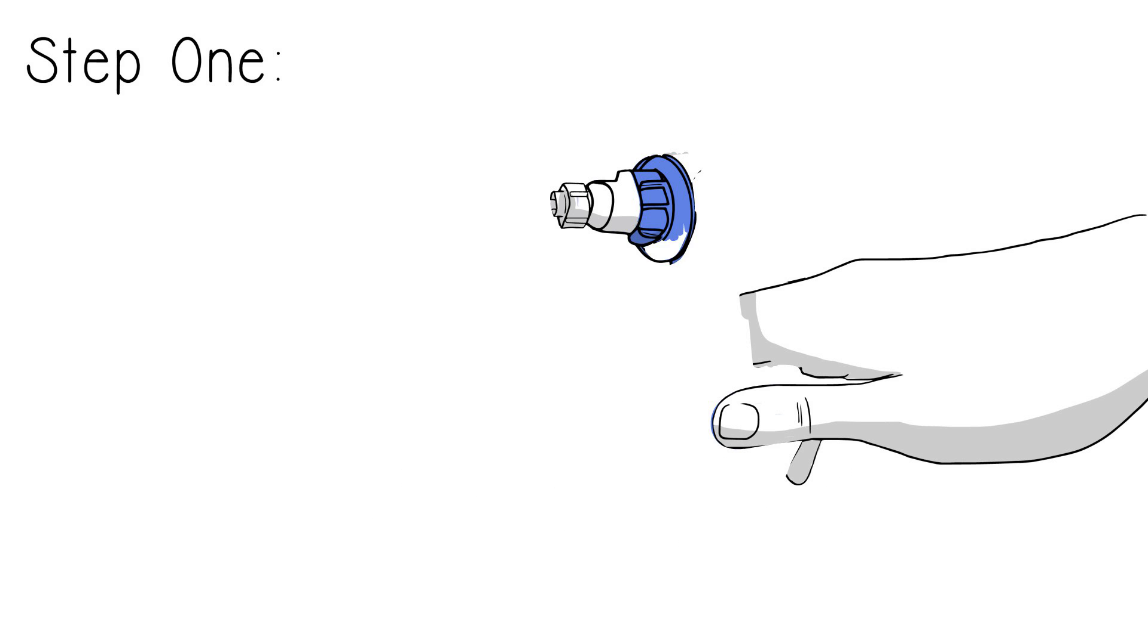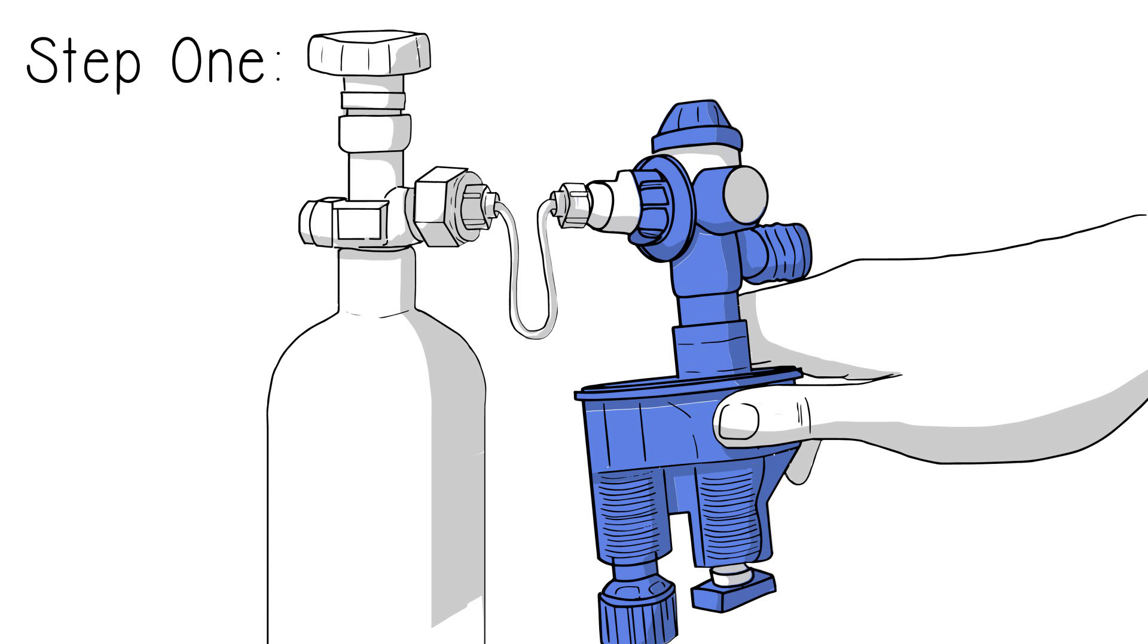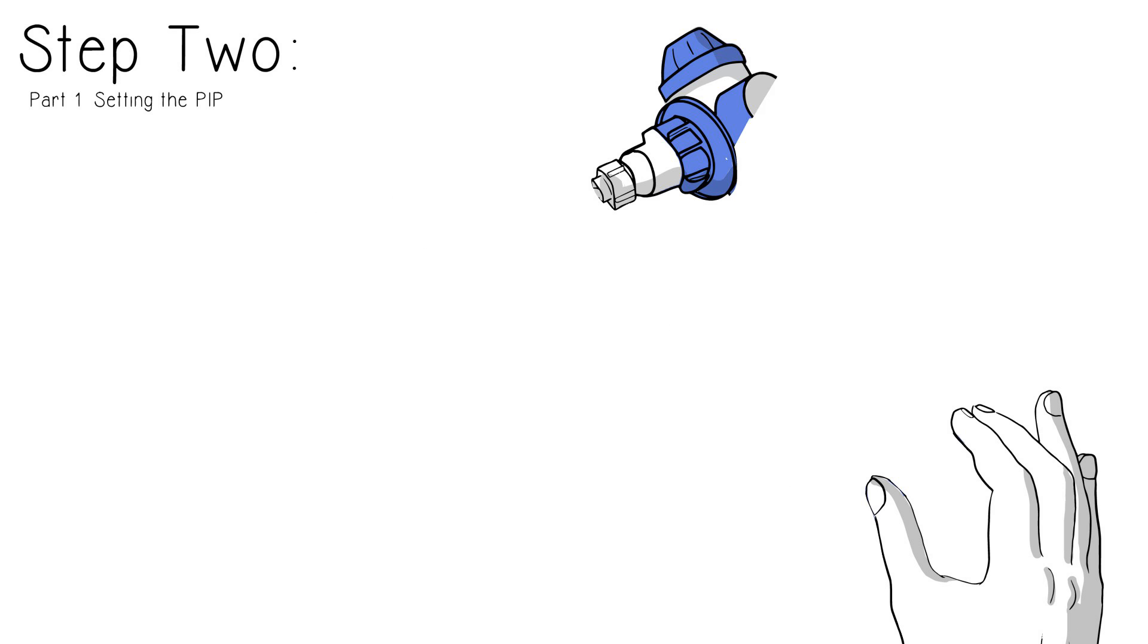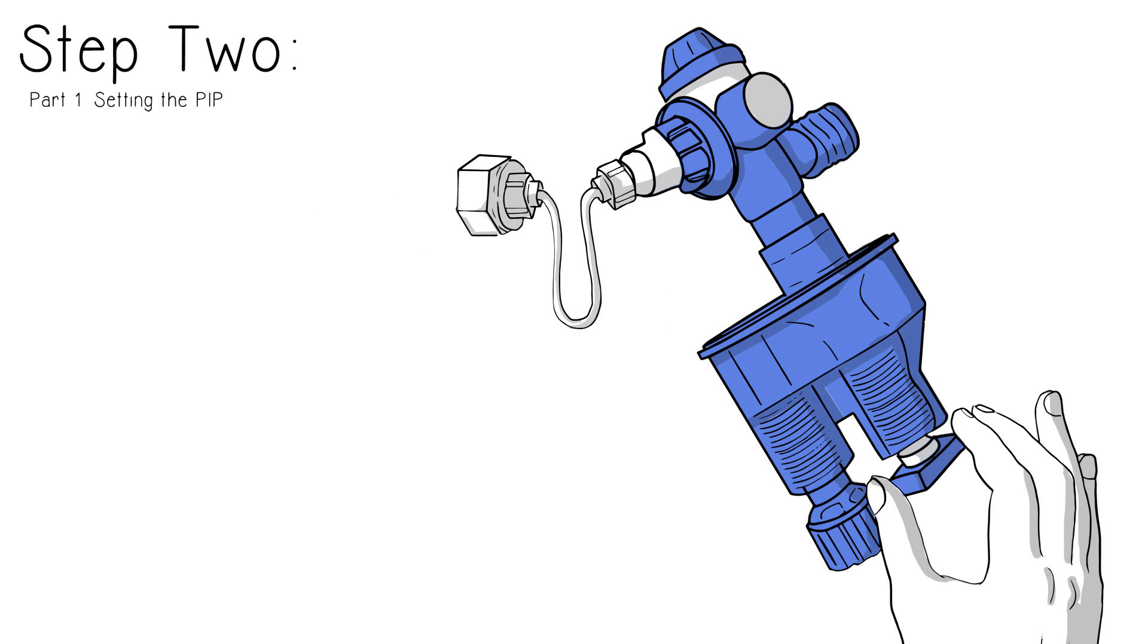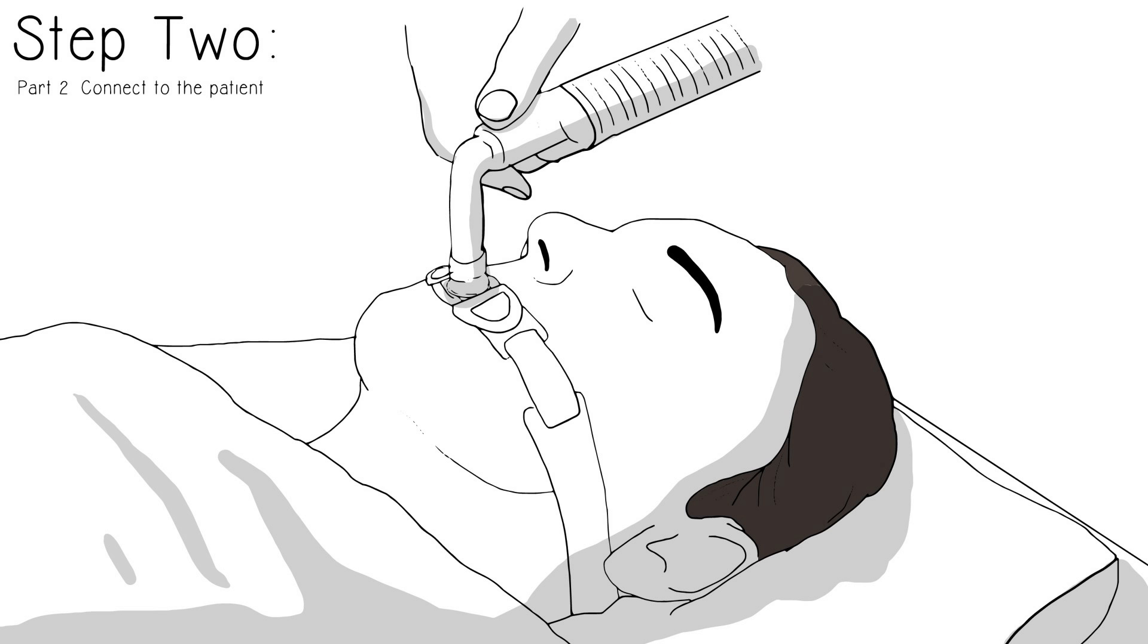It is ready to go in just three easy steps. One, connect to pressurized gas source. Set inspiratory flow, adjust as needed. Two, set PIP, peak inspiratory pressure with T-dial. Verify operation with manometer and connect a patient.